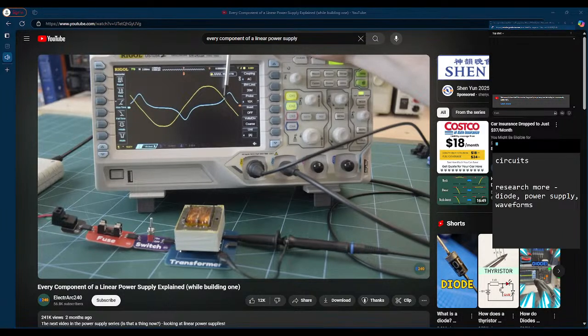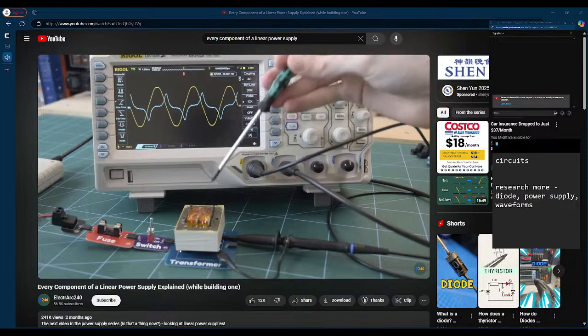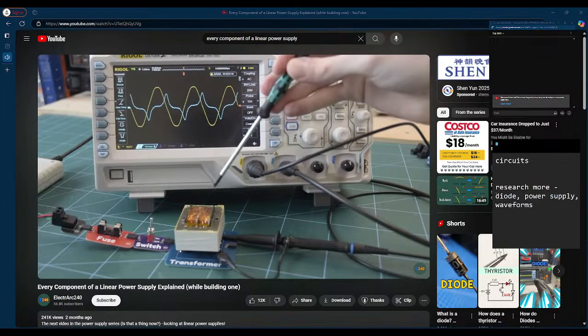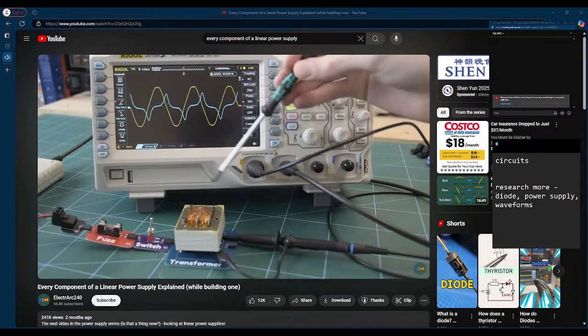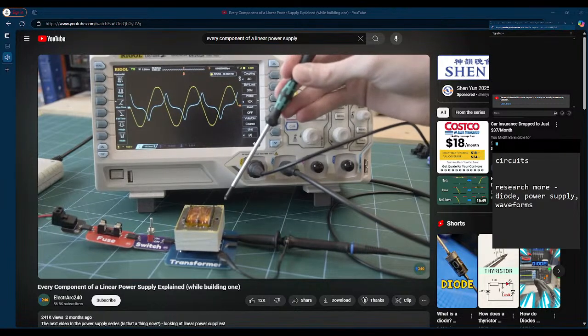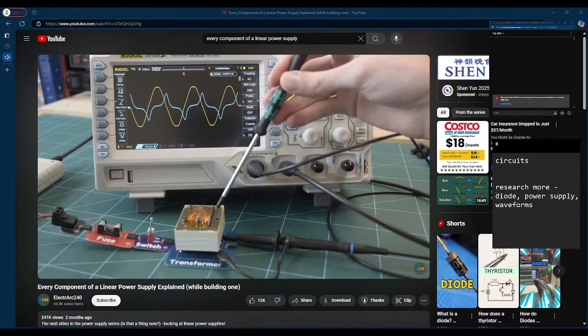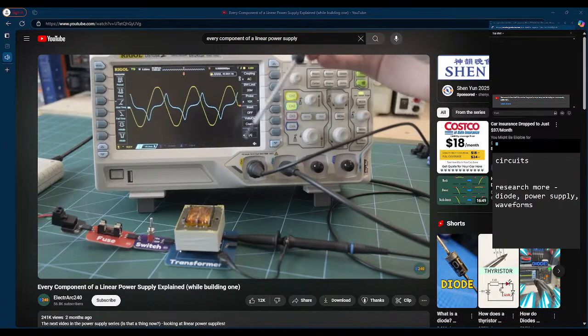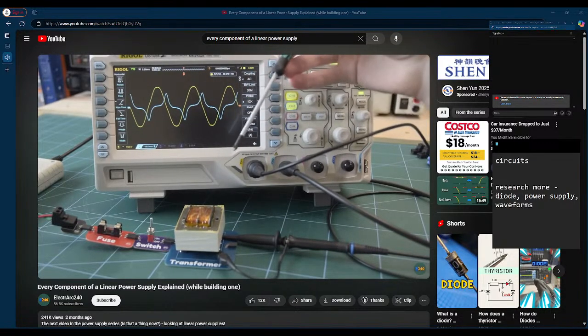Now, it's not unusual to have a little bit of saturation in mains frequency transformers, just to squeeze out as much performance as possible from a certain size. I suspect this is a little more than this transformer was designed for, because technically it's rated for 230 volts, and my mains voltage today is 247 volts, which means the area underneath this voltage curve is going to be a decent amount more than this transformer was designed for.